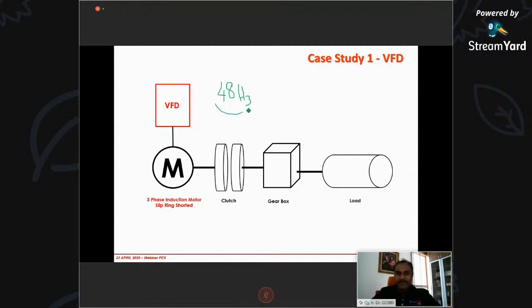And then they set the frequency to 48 hertz. Why could they not reduce more than that? Because as I told you just now, if you reduce the speed here, you are going to give a low speed here, which is going to have an impact on the load. So they just reduced it a little bit by 2 hertz, assuming that, okay, we can see a saving. But there is no saving at all.